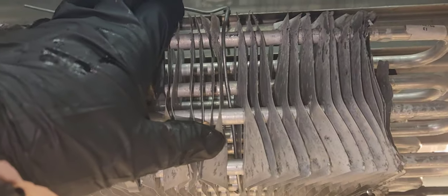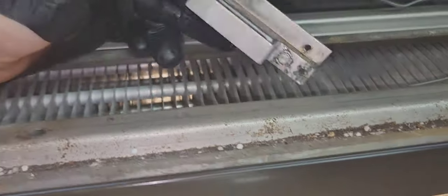Gone. All right, so this is how I supported the coil. It's holding it. I got the bracket up here. I'm probably gonna try to order another bracket though, because this one's all kind of screwed up. And I'm gonna let the top down and put it back together. I mounted my expansion valves back and my sensing bulbs with those new straps.